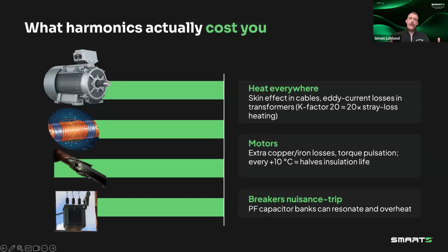From your facility perspective, what's the consequence of harmonics? The main one, and by far, is heat. Every time you have harmonics, this is energy that needs to be dissipated, that's not usable, and so it really transfers as heat, whether it's skin effect in cable or eddy current losses in transformers. Those harmonics are being translated into heat in your facility. Just a K factor 20 transformer sees roughly 20 times the stray loss heating of a standard unit. So really it counts. And that's true regardless of whether the harmonics are on the grid side or the load side. So a motor exposed to harmonics will also run hotter by having extra copper and iron losses. So it's not just something that affects the grid.